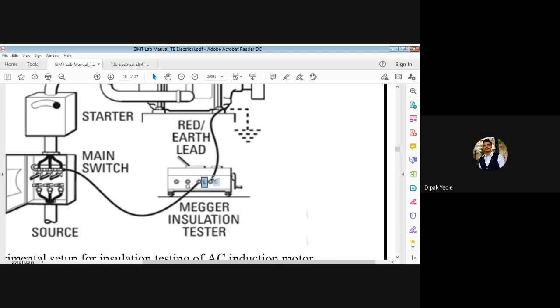We don't need to connect the G terminal, since we are not using multiple equipments in series with this motor. We have to connect the earth terminal to the earth of our motor. So the motor is here, and this is the earth terminal they have taken out, connected to this earth point.